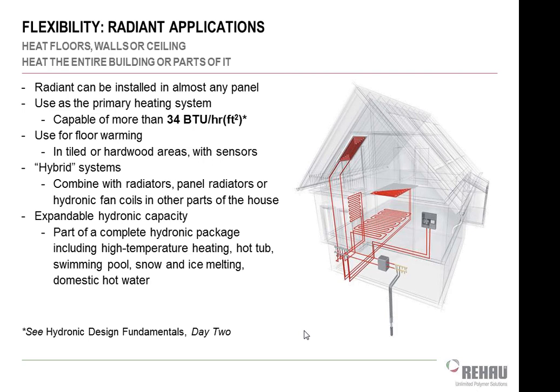You can use that same boiler to do snow and ice melt, which we'll talk about in a little bit, to clear out driveways, sidewalks, and things like that. You can use it to heat your swimming pool. You can use it with an indirect tank to heat your domestic water. I mean, once you got a boiler there and you got the burner going, you might as well put heat into every spot you can off of that one burner, as opposed to using a 50% efficient water heater. You already got a 95% efficient boiler sitting there.